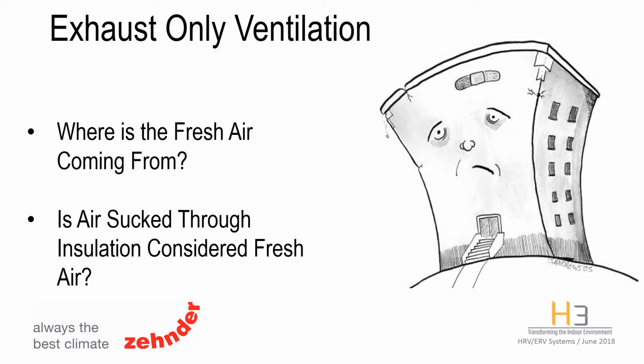It was initially thought that exhaust-only ventilation, such as a continuously running bath fan, could address the need for fresh air ventilation. But in a tight home, this has proven to be an exercise in futility. If the home is tight, where does the air come from? If you're running exhaust-only ventilation, you're creating a negative pressure environment which could pull unregulated moisture through vulnerable areas into interstitial spaces, through walls, roofs, and crawl spaces.